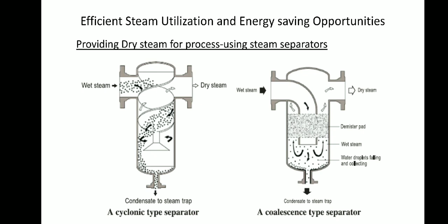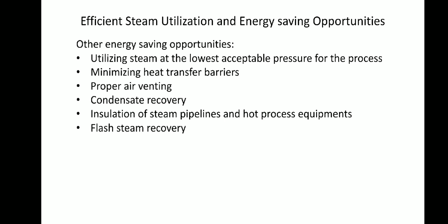Then other energy saving opportunities are utilizing steam at the lowest acceptable pressure for the process, minimizing heat transfer barriers, proper air venting and condensate recovery, and insulation of steam pipelines and hot process equipment. And finally, flash steam recovery. These are the energy saving opportunities of steam pipelines.